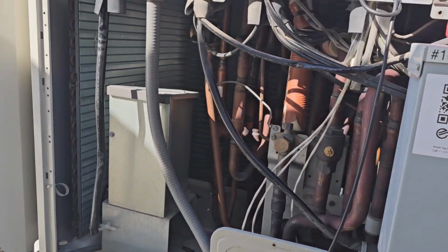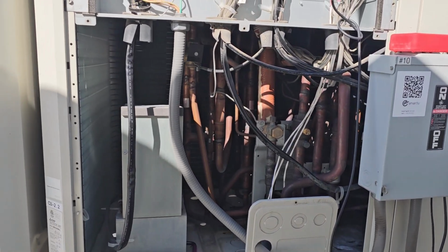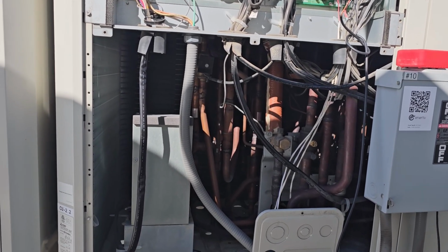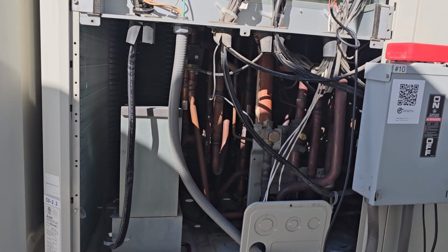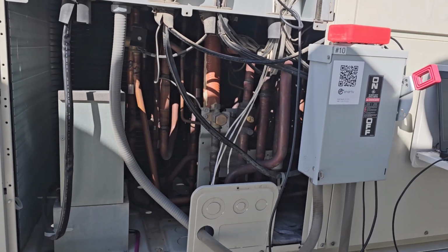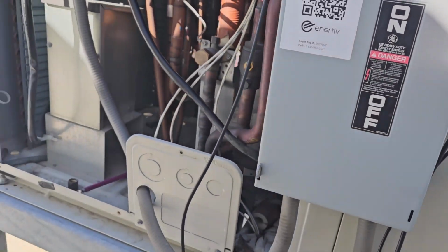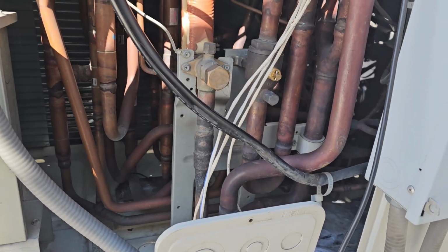Just goes to show you, no matter how long you work on stuff, no matter what it is, I work on this stuff every day, that the most basic, simplest thing can end up being the problem. I'm not going to walk up to a unit every time and assume that somebody's been here before me and shut some ball valves. I'm going to walk up, hook my laptop up, and go, whoa, why are my temperatures so weird? That's interesting. And then follow those until it leads you into checking something as stupid as, oh, are the ball valves open? You know, I'm tracing all this refrigerant out.